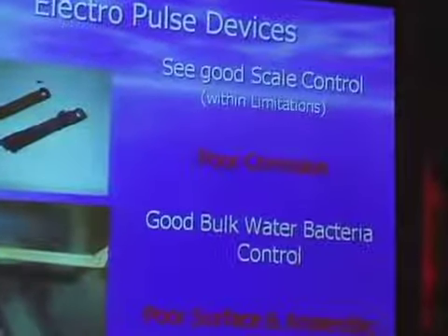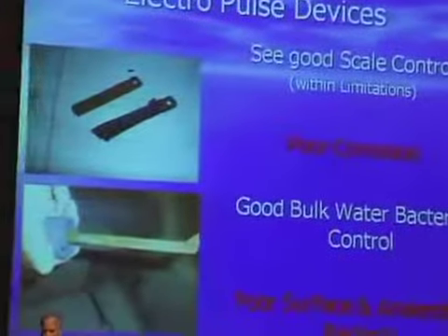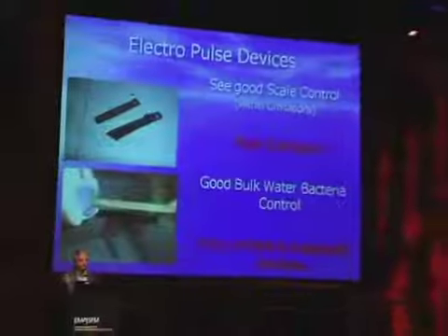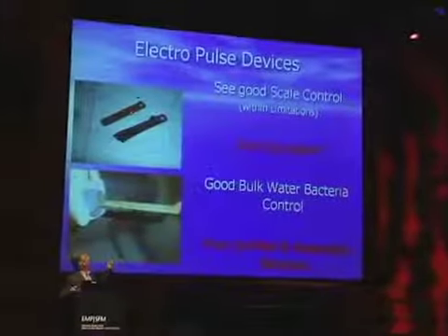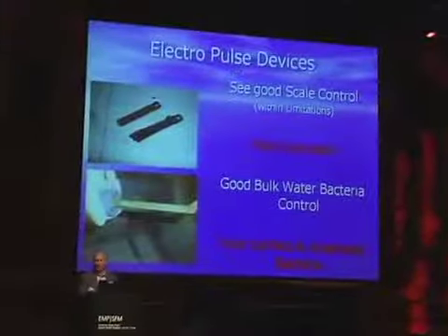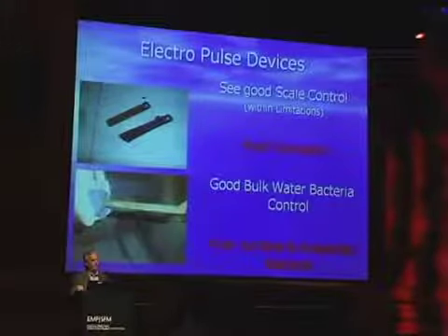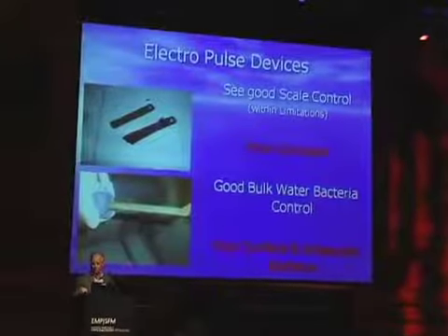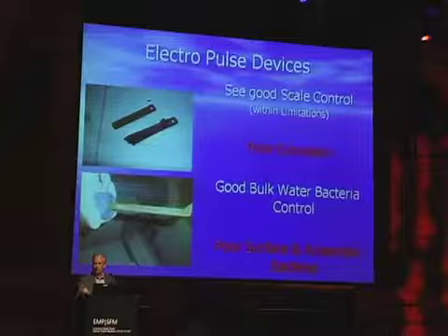We don't see good corrosion control. There are two types of corrosion: general corrosion and biologically influenced corrosion. For general corrosion we see pretty good results, like on the copper coupons we see fairly good copper corrosion results, but we don't see very good mild steel corrosion, because of biological problems.